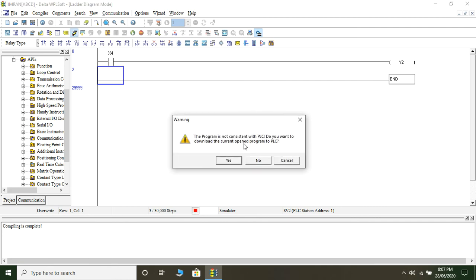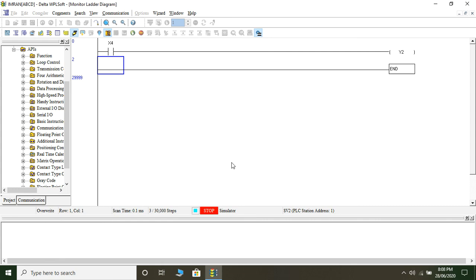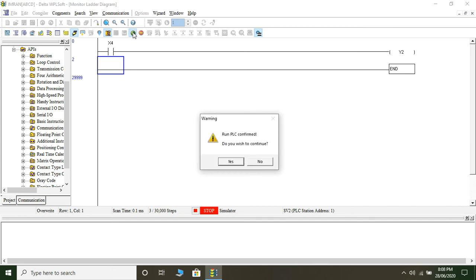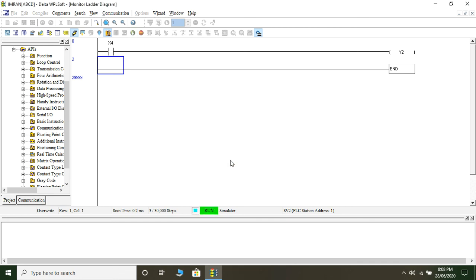It tells me the program is not consistent with the PLC, meaning it is not there in the PLC yet — do you want to download the current opened program to PLC? The answer is yes. The blue lines indicate that the program is downloaded in the PLC; however, 'Stop' at the bottom says the PLC is in stop mode. To place it in run mode we click on Run and then Yes, so now the PLC is in run mode.